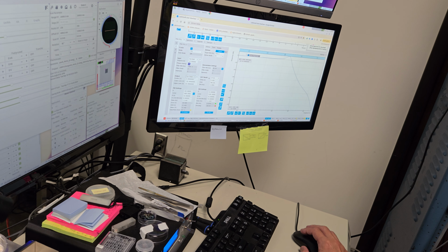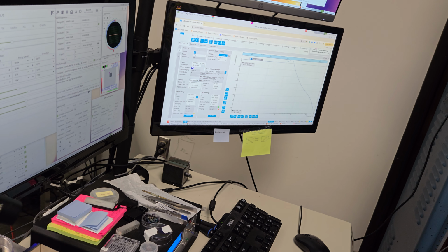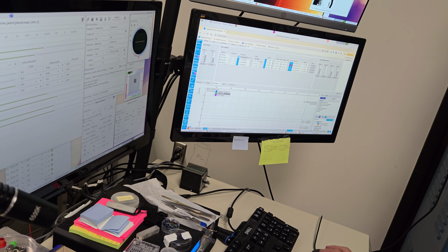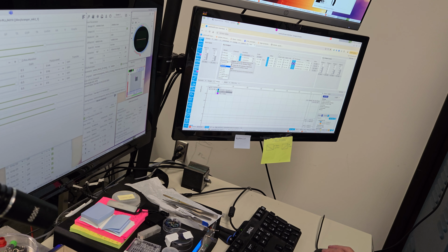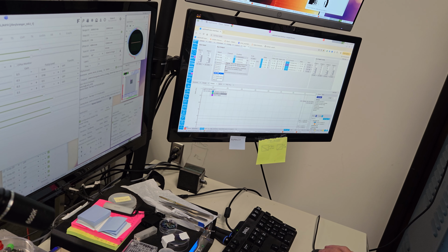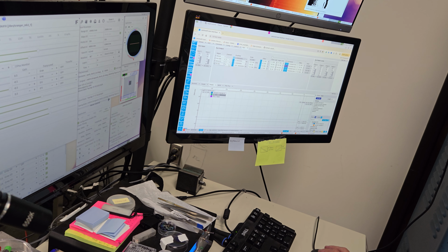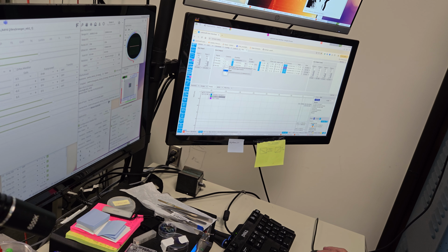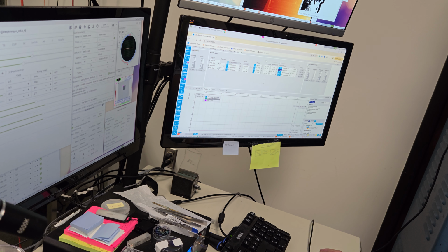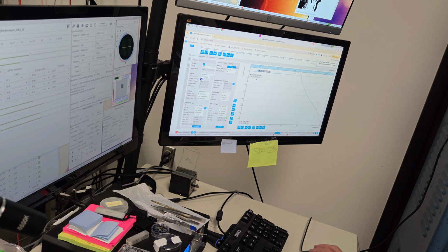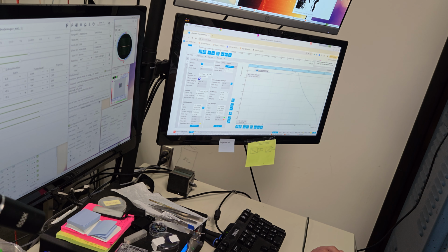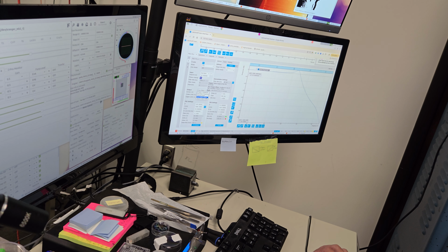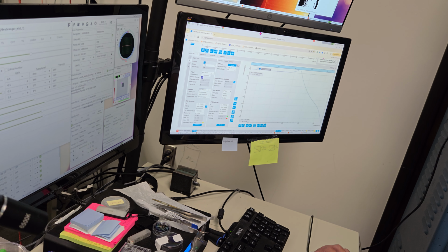I see. This is actually a bit tricky. So it appears in auxiliary output 4 as an offset. Yeah, I think we should set it this way, from a PID out. Or is it 4? Auxiliary output 4, right? Yes. PID output of 2, PID 2 output. And then instead of choosing offset, we should choose amplitude. Well, I think that's the only option. So I think we just leave it.